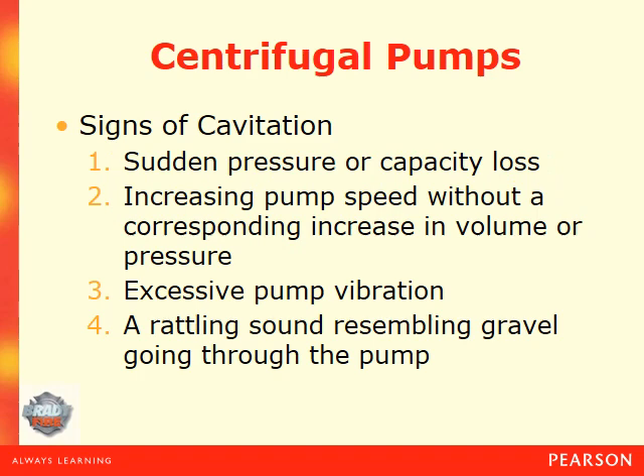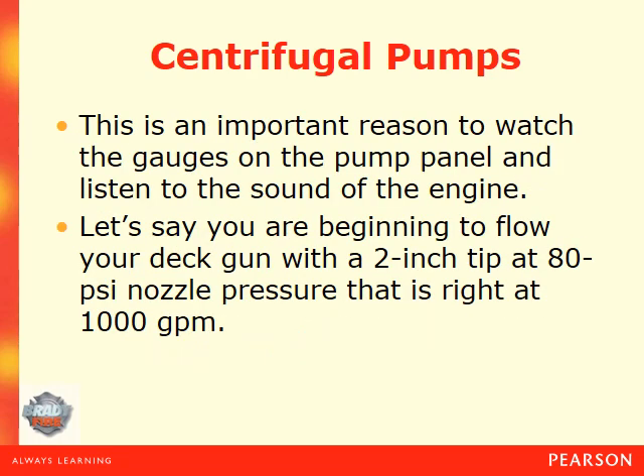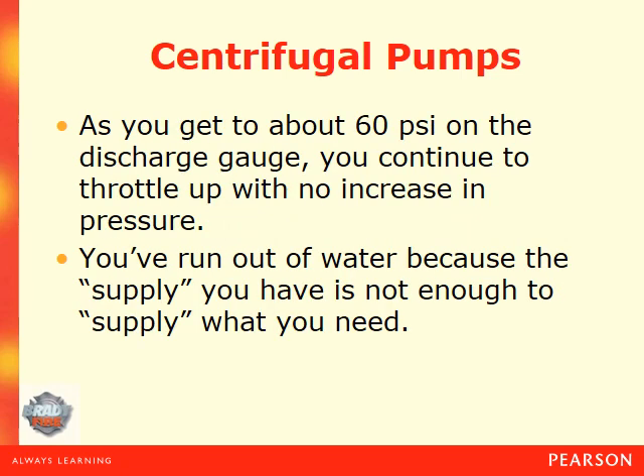Signs of cavitation include: sudden pressure or capacity loss; increased pump speed without a corresponding increase in volume or pressure; excessive pump vibration; and a rattling sound resembling gravel going through the pump. It is important to watch the gauges on the pump panel and listen to the sound of the engine. For example, if you are beginning to flow a deck gun with a 2-inch tip at 80 psi — right at 1,000 gallons per minute — and as you get to about 60 psi on the discharge gauge you continue to throttle up with no increase in pressure, you have run out of water because the supply is not enough.